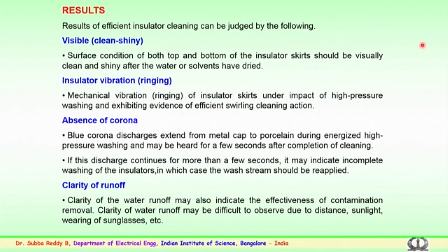The third is the absence of corona activity. Because of contaminants on the surface, it could be metallic parts, or hard dust comprising conductive dust which settles over a period of time because of fog or mist, the activity of corona starts on the surface, showing dry band and wet band, arcing, partial discharges and also corona discharges, which could extend from the metal cap to the porcelain pin to the cap of the insulator, depending upon the surface conditions during energized conditions.